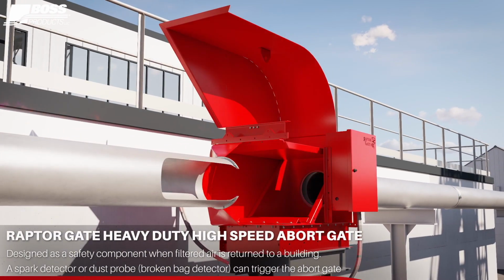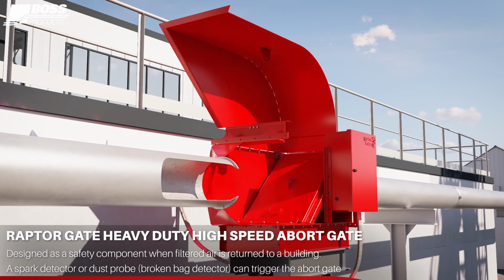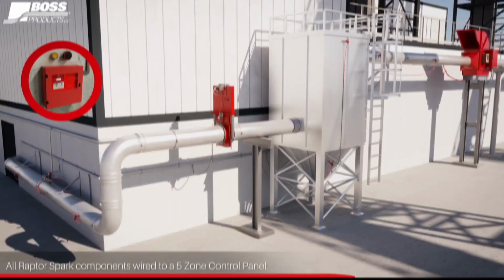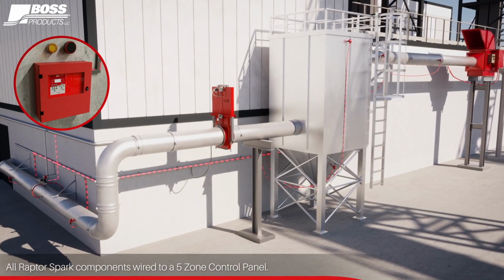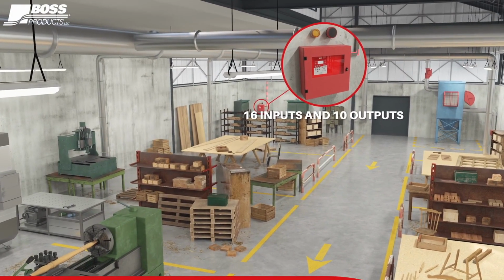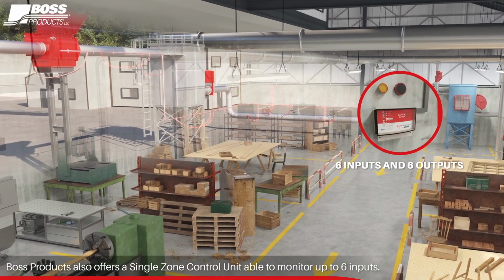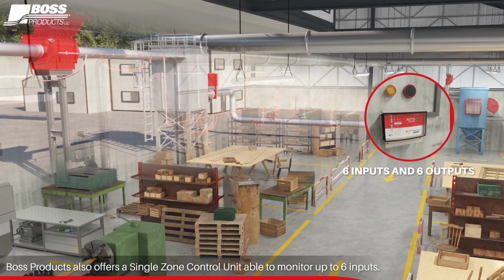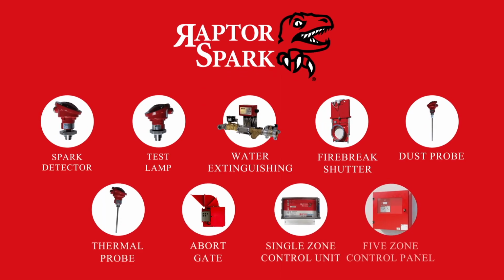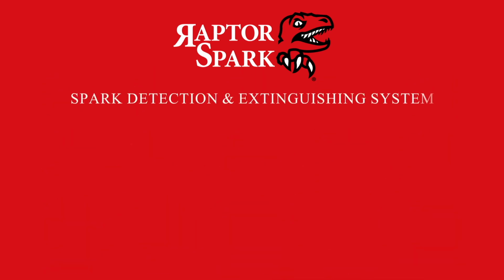And then I talked briefly about the abort gate, but that's what the abort gate looks like. It closes off the duct in the event of a triggering event of a spark, dust probe or thermal probe activation, and it closes off that ductwork. We can do different types of controls with this. We can offer different single zone controls up to a 5-zone control panel as well. So we can offer many different inputs, up to 16 different inputs and 10 outputs. Next slide, Andy.